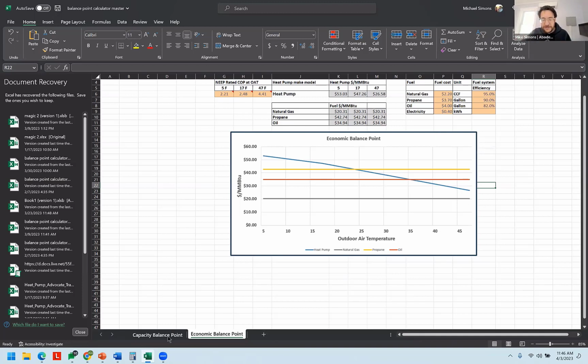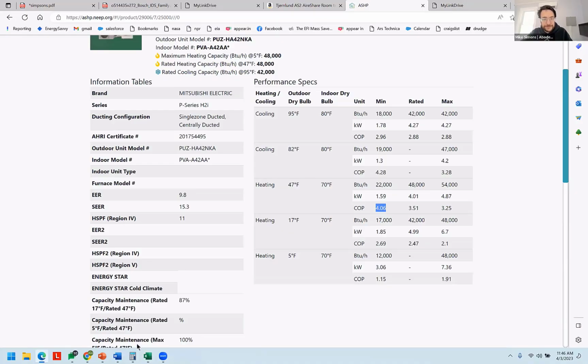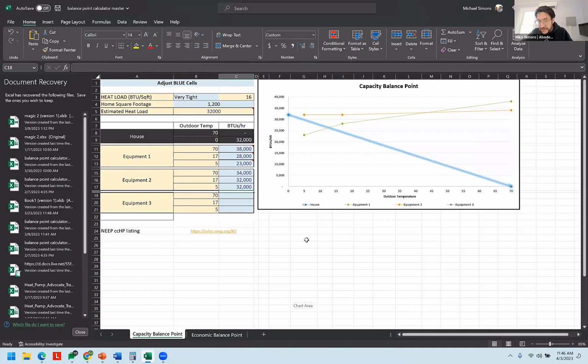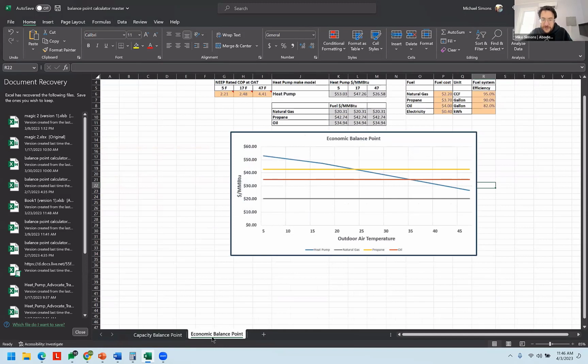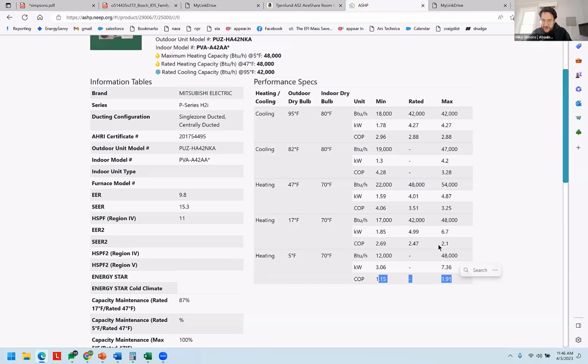And just to highlight this again, with the capacity balance point calculator that I've shared multiple times with you, the main sheet is the capacity balance point. The next tab over is the economic balance point. If natural gas is $2.20 a therm and electricity is, say, 40 cents per kilowatt hour, let me just grab the performance of this equipment. At 5 degrees, it probably has a coefficient of performance of 1.91 because it's working really hard there. At 17 degrees, it's probably going to be between those two numbers, so I'll just keep it as 2.47.